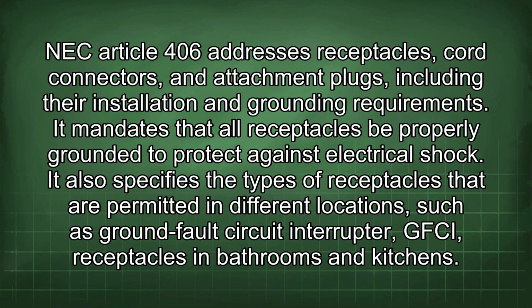NEC Article 406 addresses receptacles, cord connectors, and attachment plugs, including their installation and grounding requirements. It mandates that all receptacles be properly grounded to protect against electrical shock. It also specifies the types of receptacles that are permitted in different locations, such as ground fault circuit interrupter (GFCI) receptacles in bathrooms and kitchens.